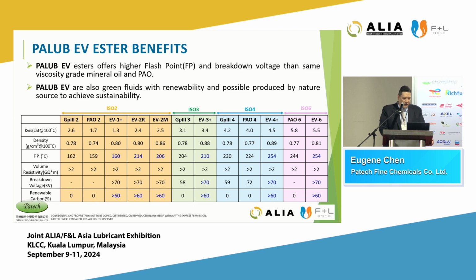The benefit of ester is that we tend to have a product with higher flash point, so we can work at higher temperatures. The breakdown voltage within the same viscosity grade is also much better than mineral oil and PAO.